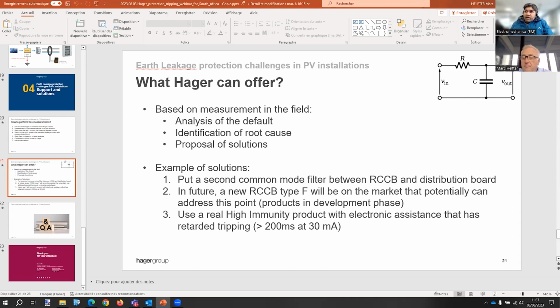No problem. Reagan did mention that these questions are related to the SANS 10142 specification. Maybe other colleagues need to review the SANS spec on the earthing sizes. Thanks, Reagan, for that. Somebody did mention anonymously, normally spec the earth cable the same as your current supply cable, although there is no normal current in the earth cable. When there is a leak, it needs to carry the load which you'll be able to produce. That's just a comment somebody made. Thank you for that.